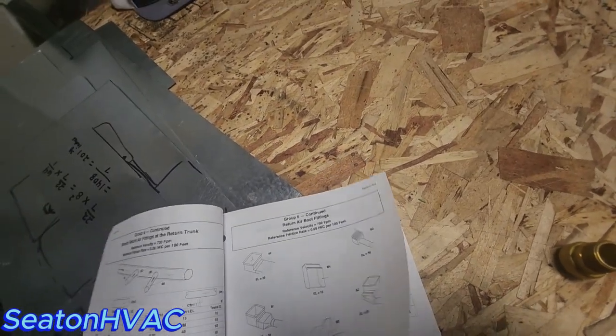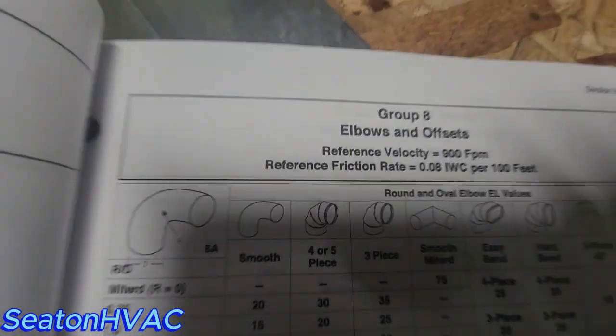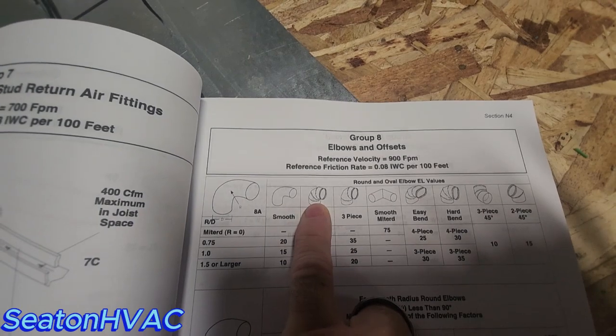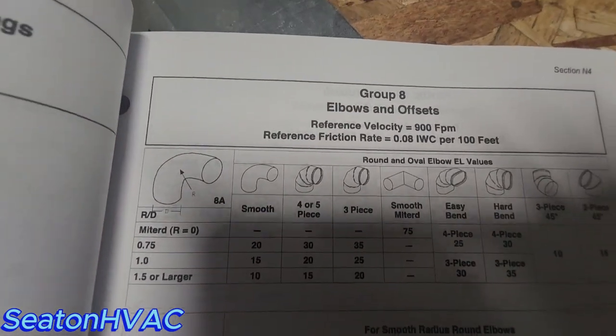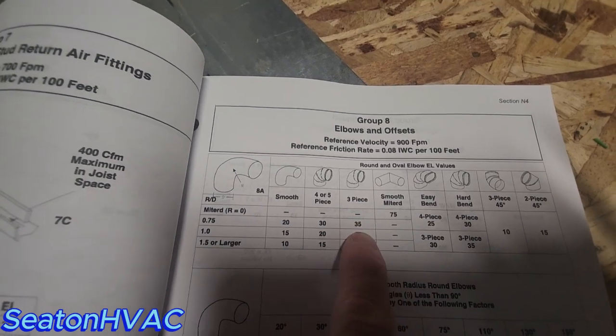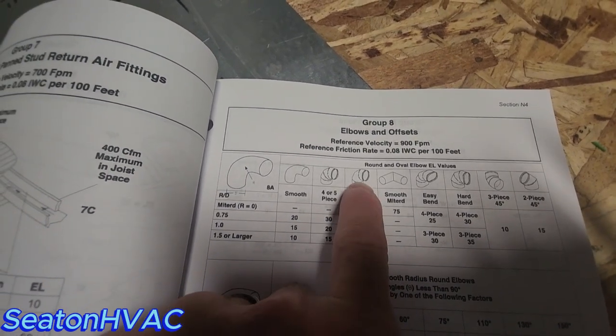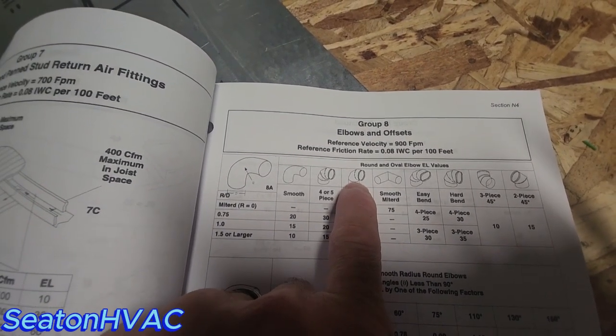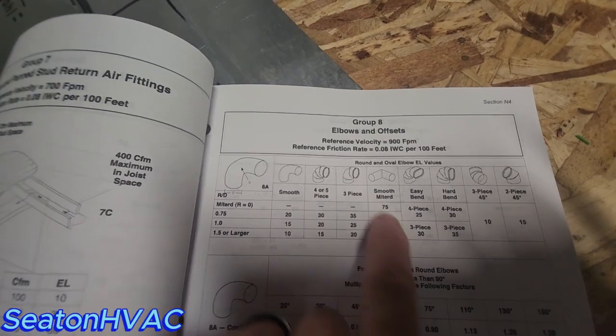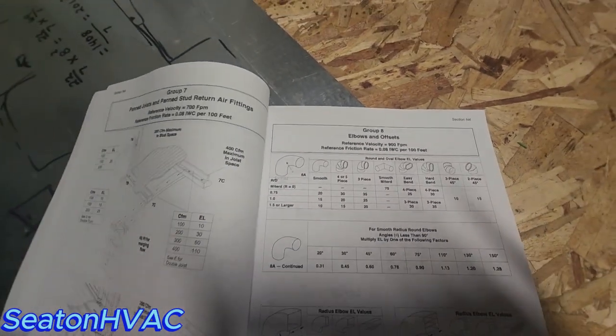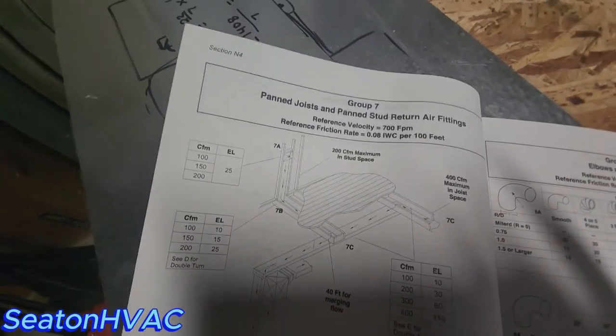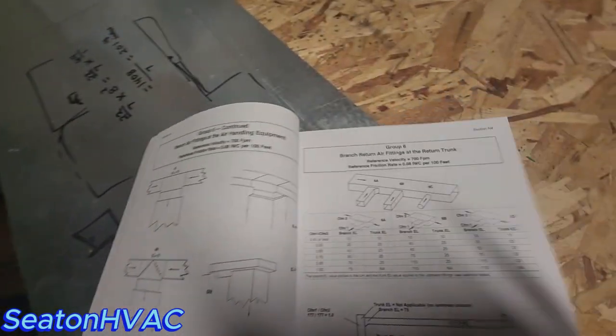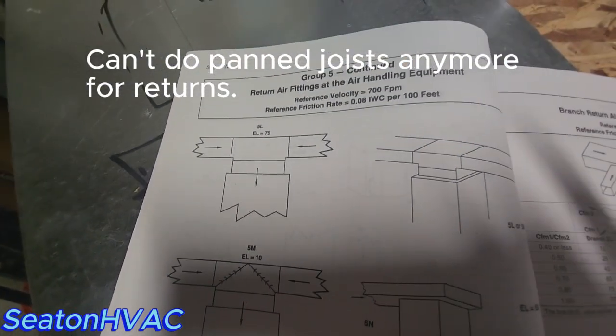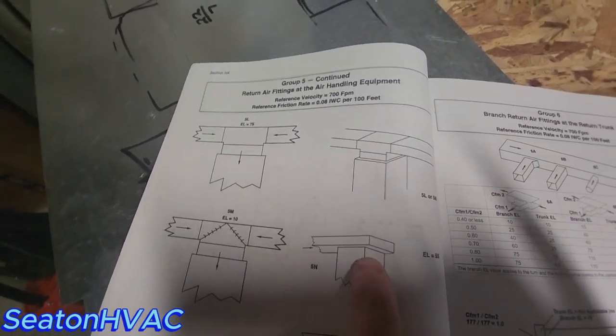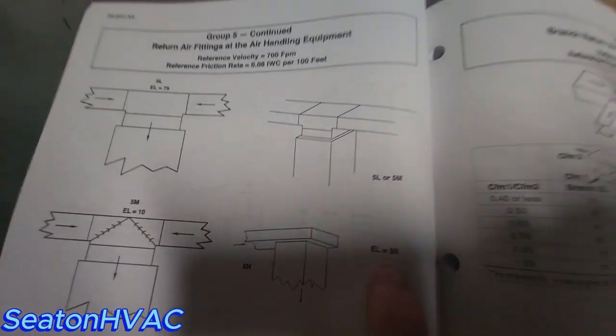Here you go. So you've got your 4 or 5 piece elbows. There's even a different total equivalent length for a 3-piece elbow, but it tells you what that equivalent length is, what it adds to the total equivalent length of your entire duct system. It even shows you panned joists, panned return airs, and if you have a return air that deadheads into a duct, what that equivalent length is.